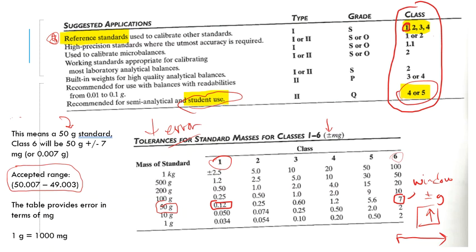And actually, this is a mistake. So if I take 50 plus 0.007, I'm going to get 50.007, right? I mean, that kind of makes sense. That's easy to do in my head. But if I take 50 minus 0.007, that is not 49.003. So I want you to double check that number in the calculator, because this number, Tracy made a mistake. Oh no! But I do that very often. So just take 50 minus 0.007 and you'll get the proper mass range that calibration weight should fall in.